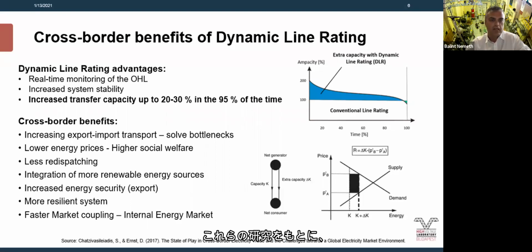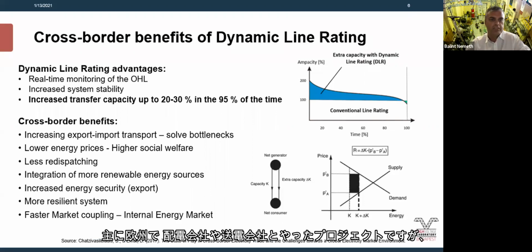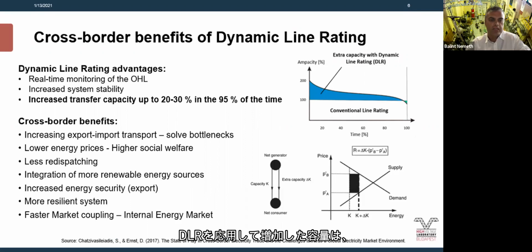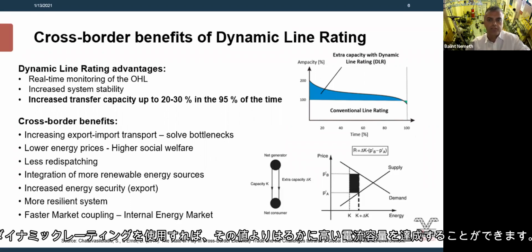Based on this research, done mainly in Europe with different distribution and transmission system operators, we see that increased transfer capacity can be up to 20 to 30% in 95% of the time. On the right, you can see the conventional line rating versus a much higher ampacity achieved using dynamic line rating, over a relatively short period.